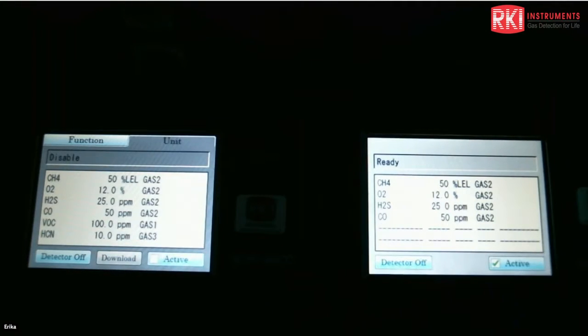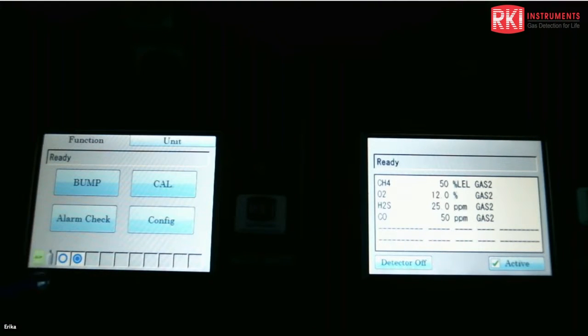So if I just want the second dock, I can still just press disable or active on that, and it's going to run the gas through there. This one is disabled, and you can kind of see the status on the bottom. The one with the dot in the middle means it's connected and it's active. If it's just a circle, it means it's disabled and not connected. So if I do a bump test, it's just pretty much going to bump test whatever is active, which is the second dock. So I'll go and put that back. And so now that both of them are active, you can see that there's the circle in the middle. So yeah, I think that should be it for the standalone.